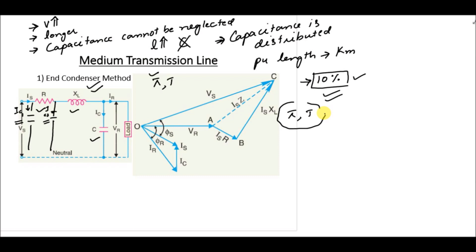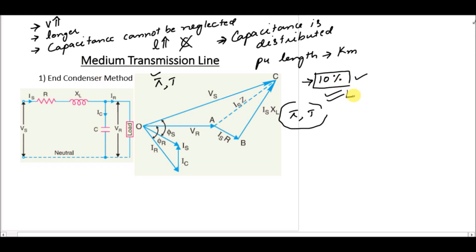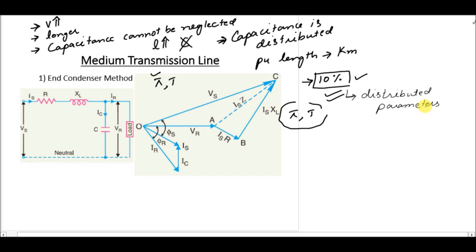This is the model of the end condenser medium transmission line. The error in the line calculation can be reduced by switching to distributed parameters rather than lumped parameters, because in the end condenser method the line capacitance is overestimated — we are overestimating the effect of line capacitance.